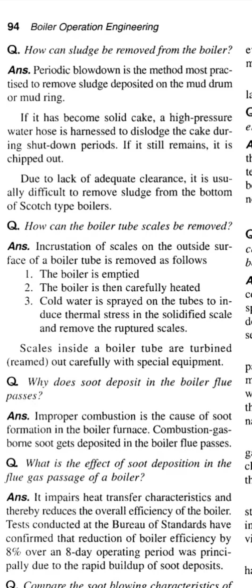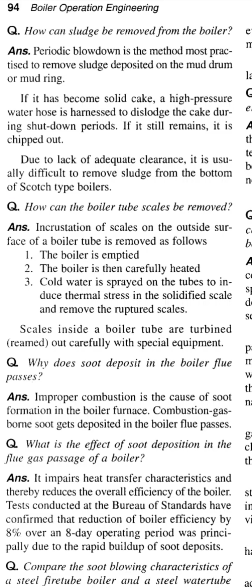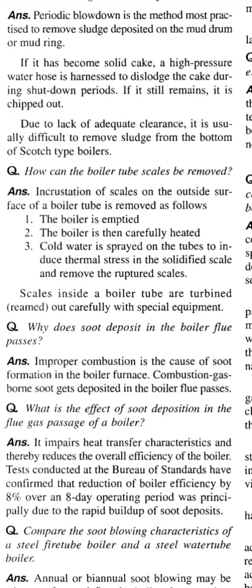Question: how can the boiler tube scale be removed? Answer: incrustation of scales on the outside surface of a boiler tube is removed as follows. The boiler is emptied. The boiler is then carefully heated. Cold water is sprayed on the boiler tubes to induce thermal stress in the solidified scale and rupture the scales. Scales inside a boiler tube are turbined or reamed out carefully with special equipment.